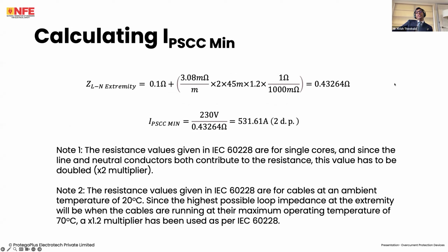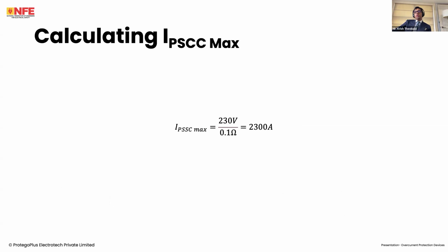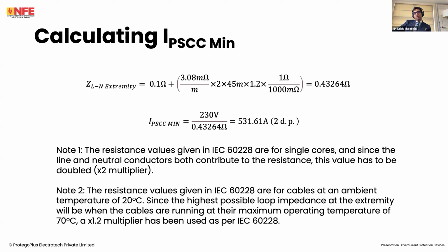What is the short circuit current at the extremity? 3.08 milliohms per meter. Here we are not considering an armored cable. We are simply considering two copper conductors, times 2 times 45 meters. That's the length of the run. Times 1.2 to correct from 20 to 70 degrees, because like I said, the resistances are given at 20 degrees. Correct from milliohms to ohms and add it to 0.1, which is the source. At the extremity, we have 0.43264 ohms. Minimum fault current is 230 divided by this value, 531 amps. So we have a range of possible short circuit currents from 2300 amps to 531.61 amps.